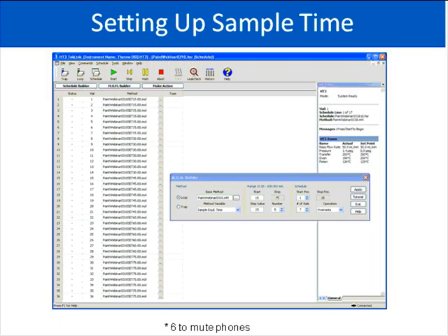Again, to set that up with M.O.M, we set up a method. We chose sample equilibration time. We started at 15 minutes. We stepped the values at 15 minutes per each step. We wanted 5 steps to get to 75 minutes. And we had 7 samples per each step. Again, once we clicked apply, it set up the entire method for us. We put the vials in and pushed the run button.